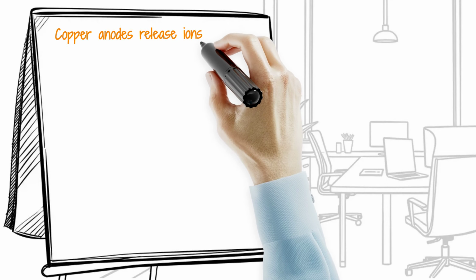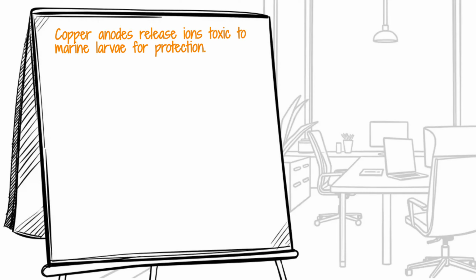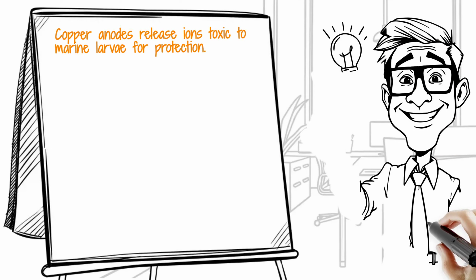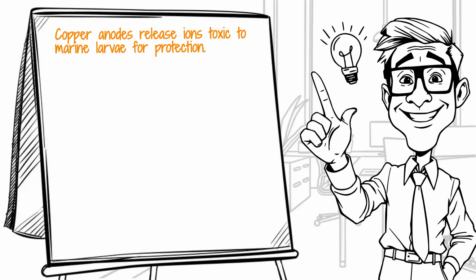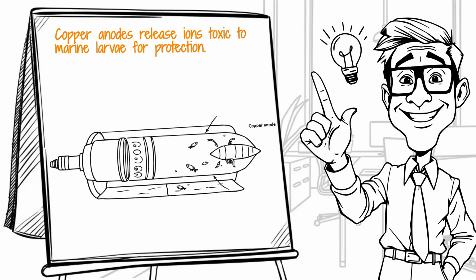The first is a copper anode. When a low-voltage direct current is passed through this anode, it slowly erodes, releasing cupric ions into the water. These copper ions are toxic to marine life larvae, preventing them from settling and beginning to grow inside the cooling system. This forms an effective, continuous barrier against macrofouling.